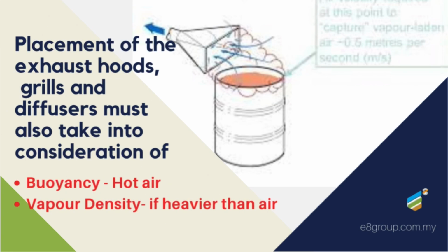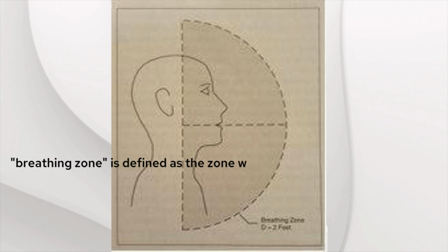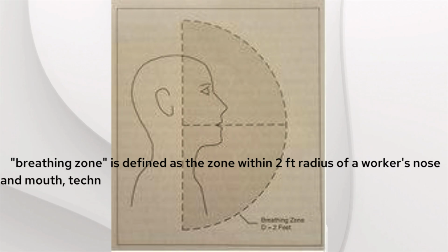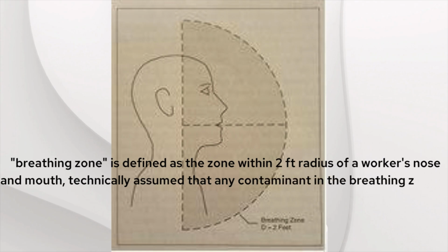Or it's a type that is highly volatile and there are a lot of people working directly in the vertical trajectory of the movement of air. You see, local exhaust ventilation's function is to remove the contaminant away from the breathing zone, right? So do you want to introduce a LEV system which moves the air to the top if the contaminant is directly below the nose of the particular person? So you've got to look into that factor when you're designing too.